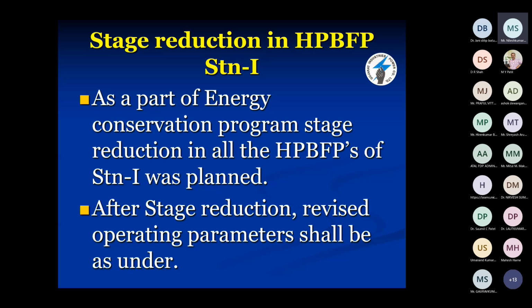Now, one another project, that is stage reduction of HPBFP. HPBFP, that is high pressure boiler feed pump. As you all know, the boiler feed pump is for feeding water into the boiler, and it is consuming very high energy. So when it is running at part load operation, the requirement of water is very low, and so we have carried out one study, and as a part of the energy conservation program, stage reduction in all the BFP pump station was planned.